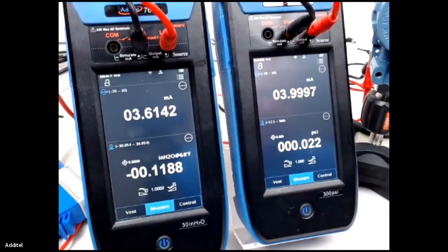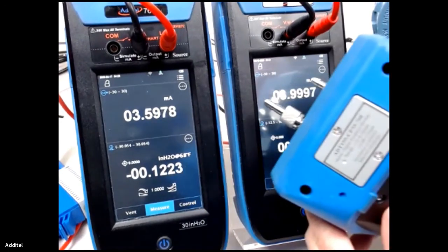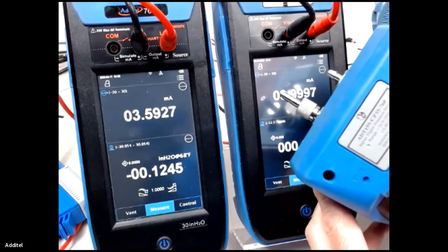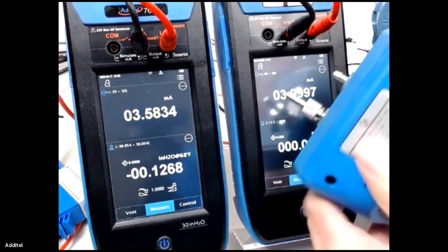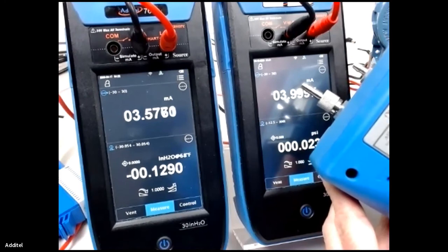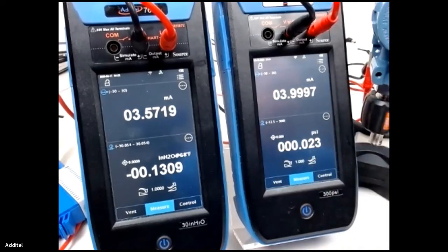The other thing that they have is a module that is interchangeable, and that depends on the range you get, but that's right in the back of the unit. So you can just unscrew the screws and change the modules. That really helps you with improving the accuracy that you need. So maybe if you're doing a 1 inch of water calibration and you've really got to nail that, we can go down as low as even a 1/4 inch of water with our modules. So we have a really wide selection of modules, and they're very easy to interchange in and out. So that's probably the first thing as far as features of the unit goes.